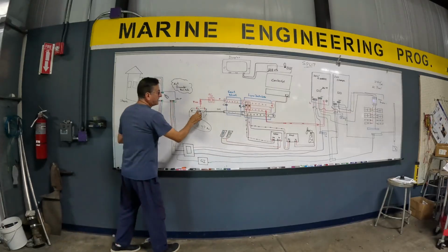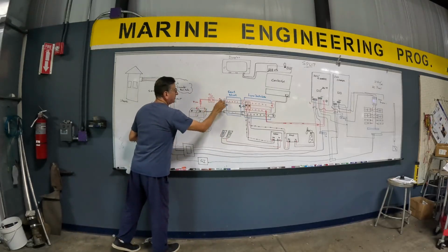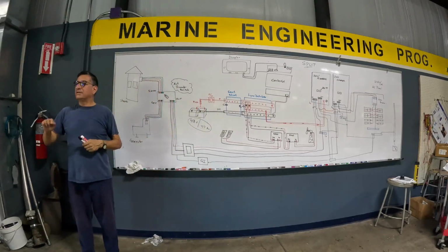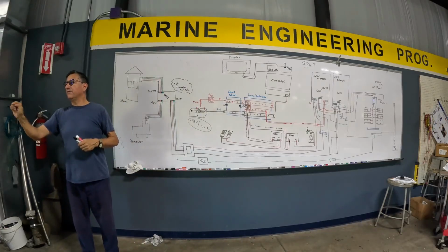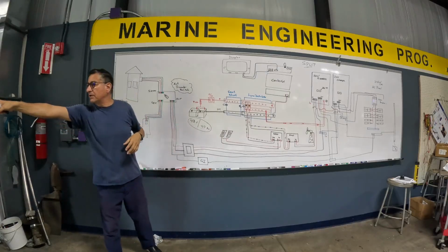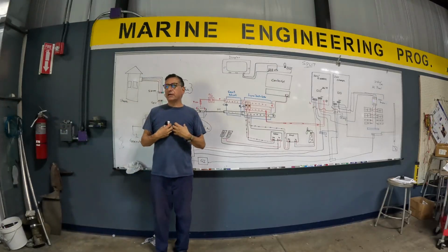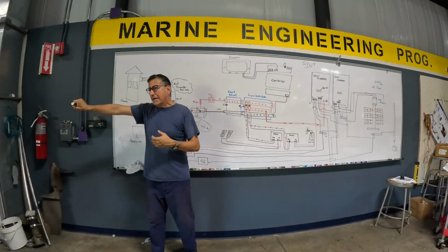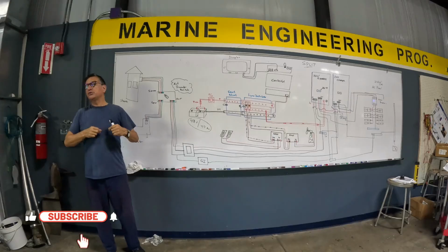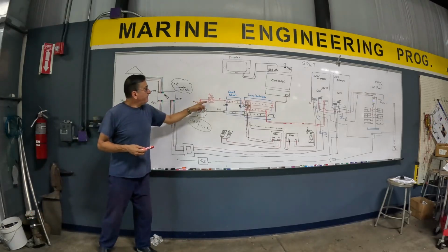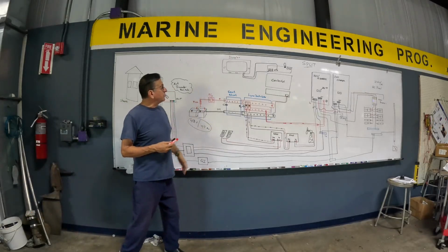The length of this positive cable and this negative cable should be identical, if it's possible. The same length of positive and the same length of negative, because normally this battery bank is not pretty close to the smart shunt. That battery bank is over there and the smart shunt is here, and you need to pass the cables positive and negative. Try to measure that both distances are pretty similar. That's okay? Good? Alright, positive and negative, and after that enter into the smart shunt.